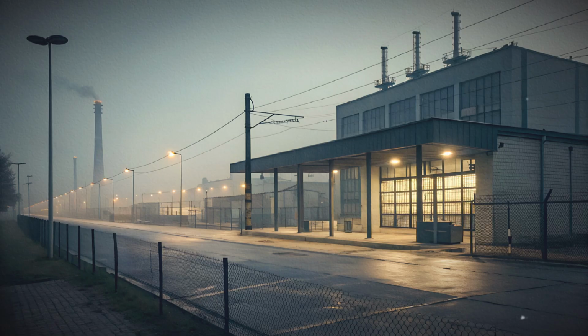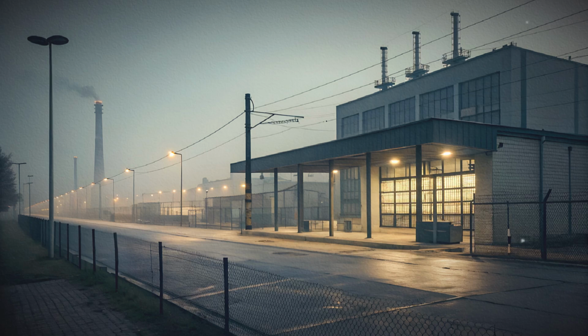Inspection techniques have diversified. Visual inspections remain common for accessible equipment. Infrared imaging detects hotspots in electrical connections. Dissolved gas analysis helps assess transformer insulation health. Drones and aerial platforms inspect lines and towers in remote or difficult terrain. Some inspections use remote cameras and robotic devices for confined spaces. Each technique contributes specific information about the condition of equipment.